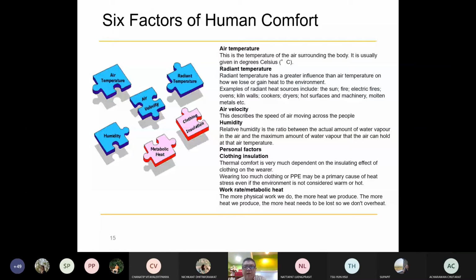Most of the time, EGAT says that 25 degrees Celsius is best for setting room temperature. But that's only one part — they don't mention the relative humidity in the room. Basically, the air conditioning units you buy will create that temperature: if you set it at 25 degrees Celsius, the relative humidity will be around 55 to 60%. So air temperature is the first factor in human comfort.